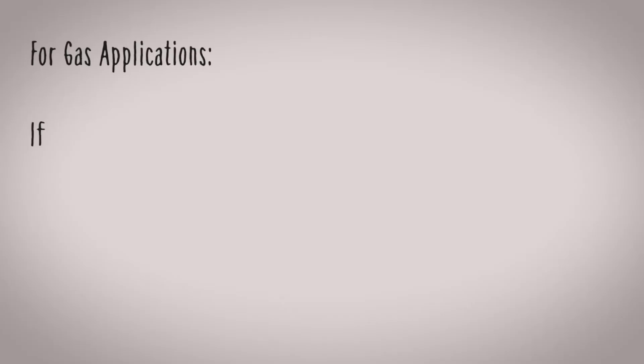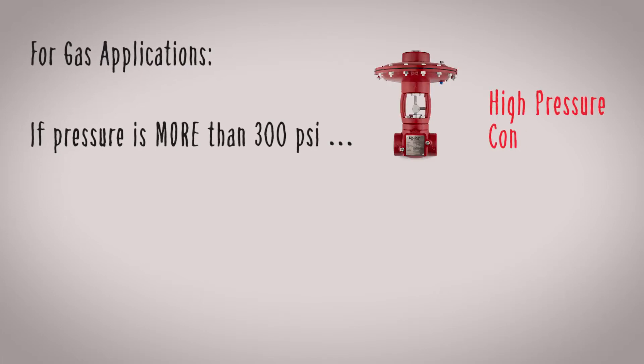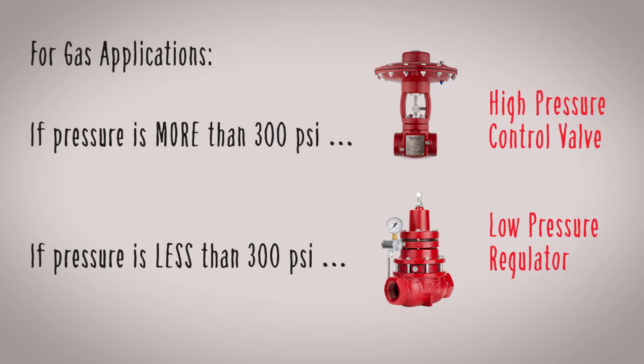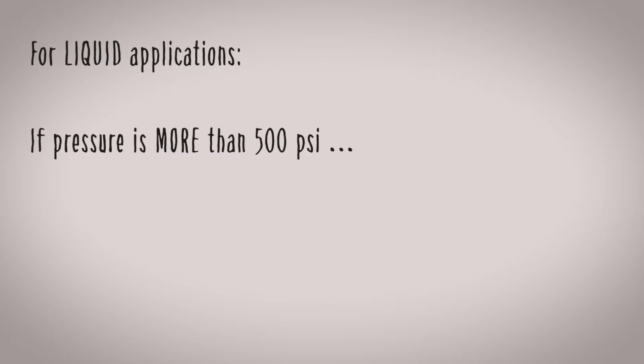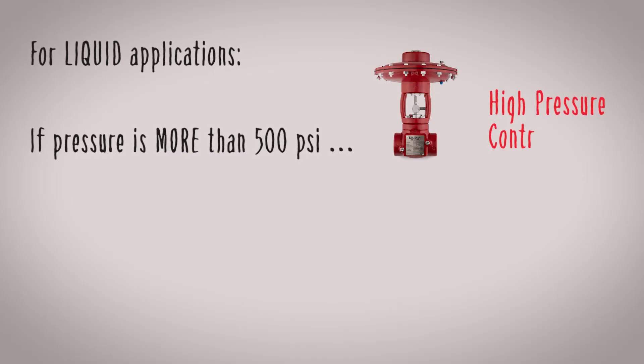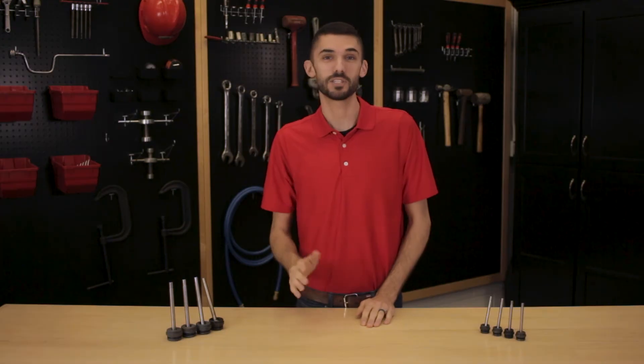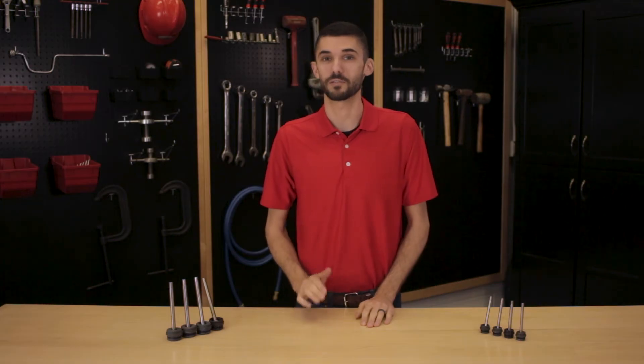For gas applications, if your pressure is more than 300 psi, you need a high pressure control valve. If it's less than 300 psi, you can likely use a low pressure regulator. For liquid applications, if your pressure is more than 500 psi, you need a high pressure control valve. If it's less than 500 psi, you can use a mechanical or pneumatic dump valve.